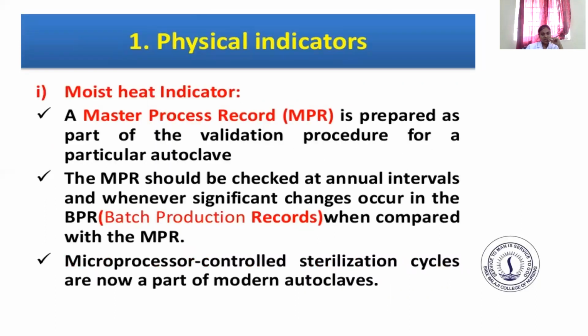Let me see the physical indicators. First one, moist heat indicator. A Master Process Record, it means MPR, is prepared as part of the validation procedure for a particular autoclave. The MPR should be checked at annual intervals and whenever significant changes occur in the BPR, it means batch production records. When compared with the MPR, microprocessor control sterilization cycles are now a part of modern autoclaves.